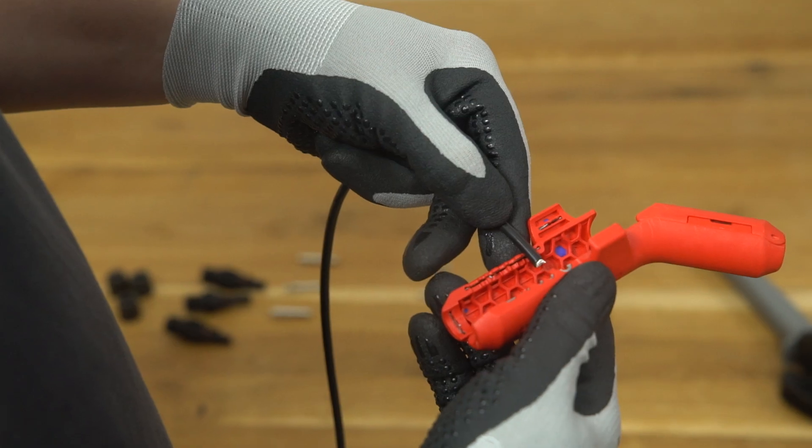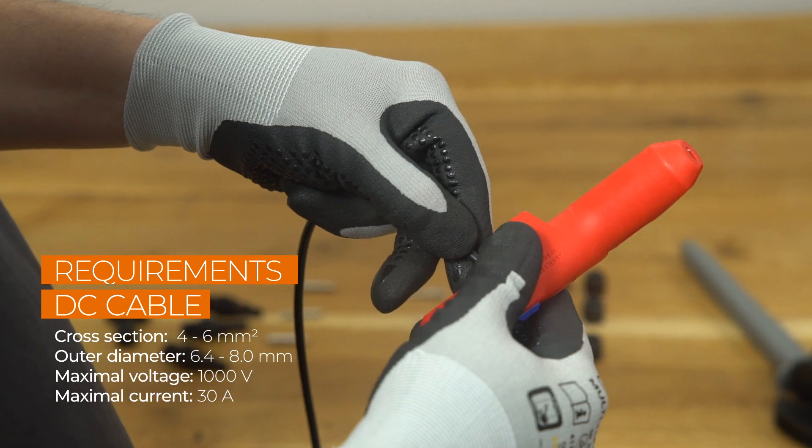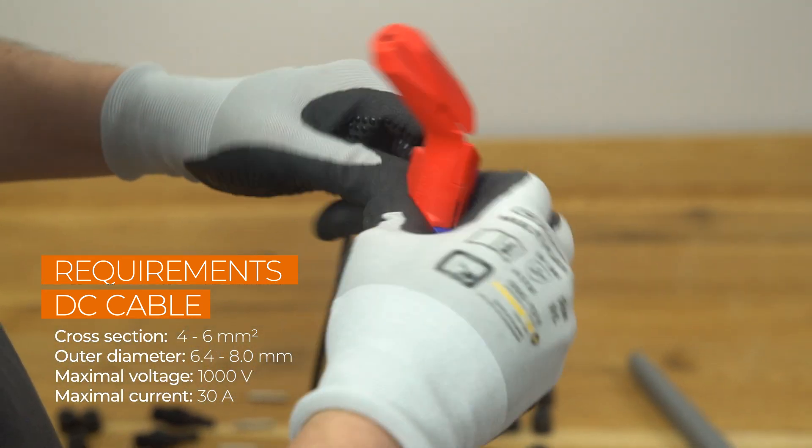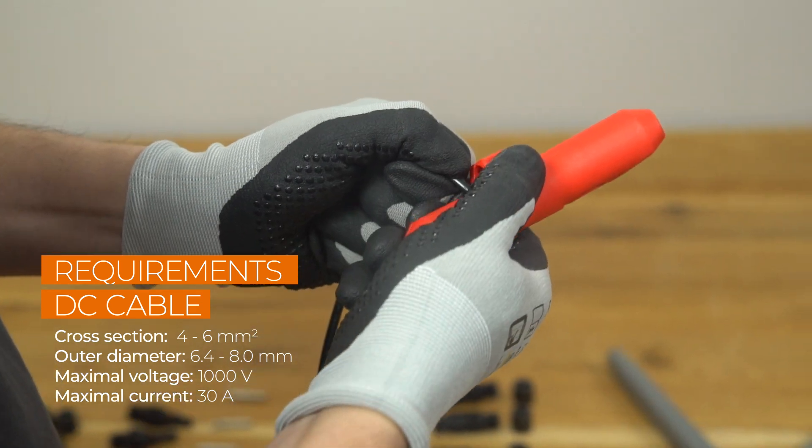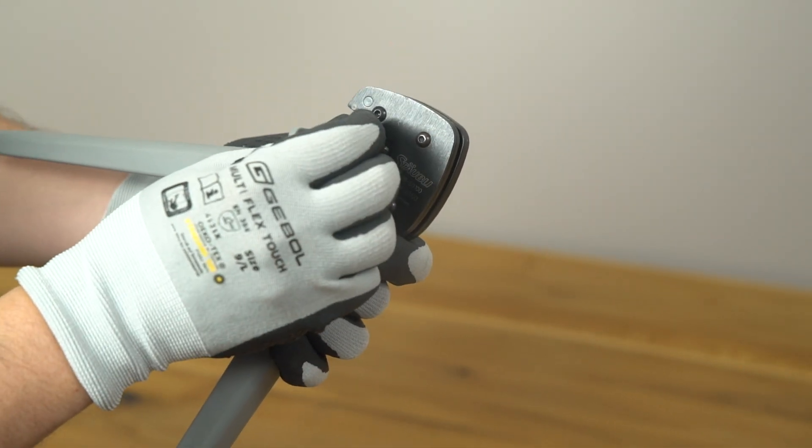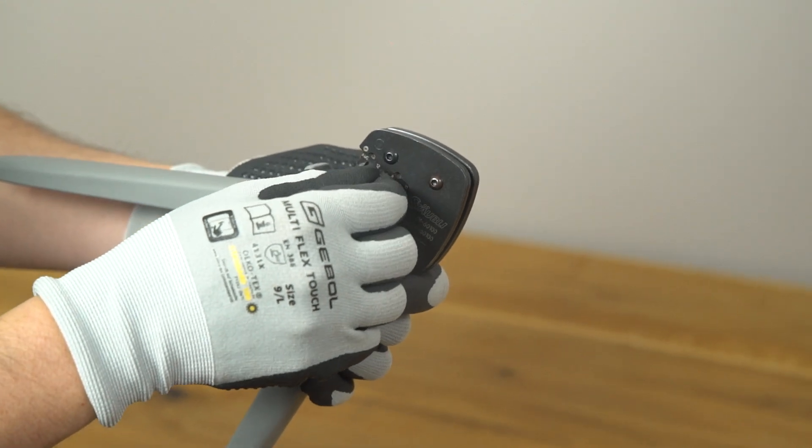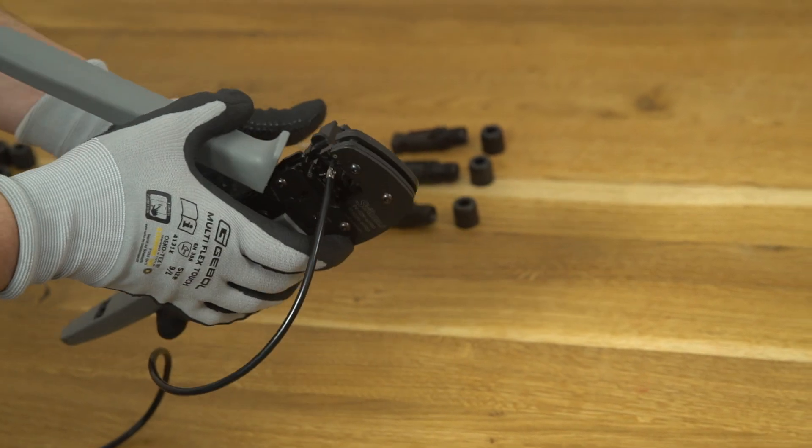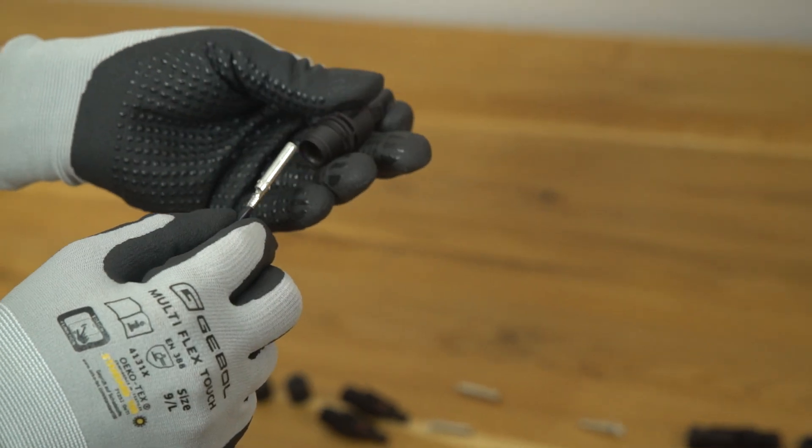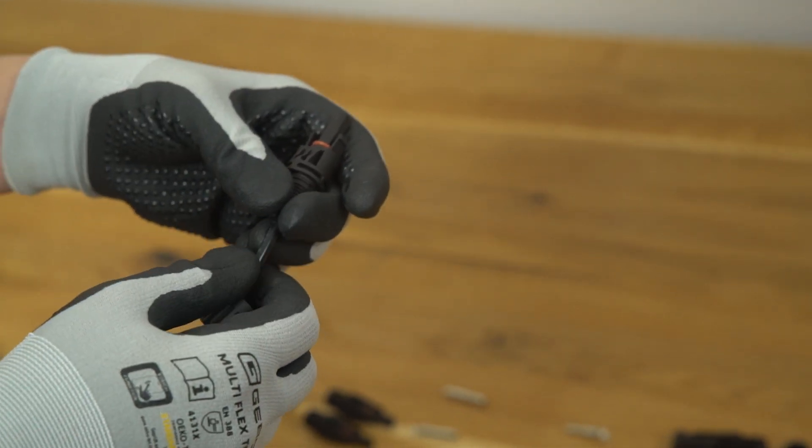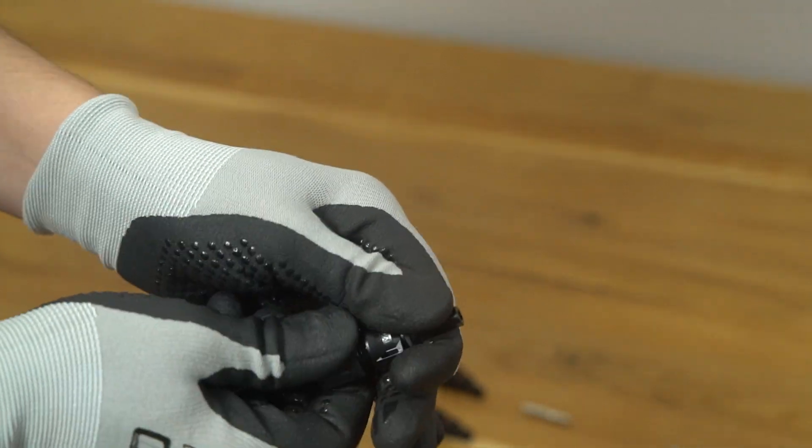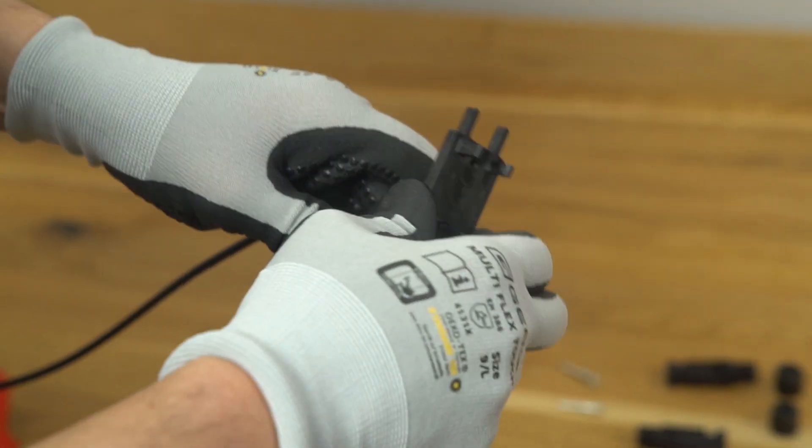Now let's take a look at the DC connectors. You have to assemble the cable ends with the crimping pliers. One is negative terminal, one is positive terminal. Lead the cable through the cable gland and insert the crimp contact into the insulator until it snaps into place. Gently pull the cable backward to ensure firm connection. Tighten the cable gland and the insulator. Pre-fasten the MC4 terminal by hand, then fasten the terminal with the MC4 wrench.